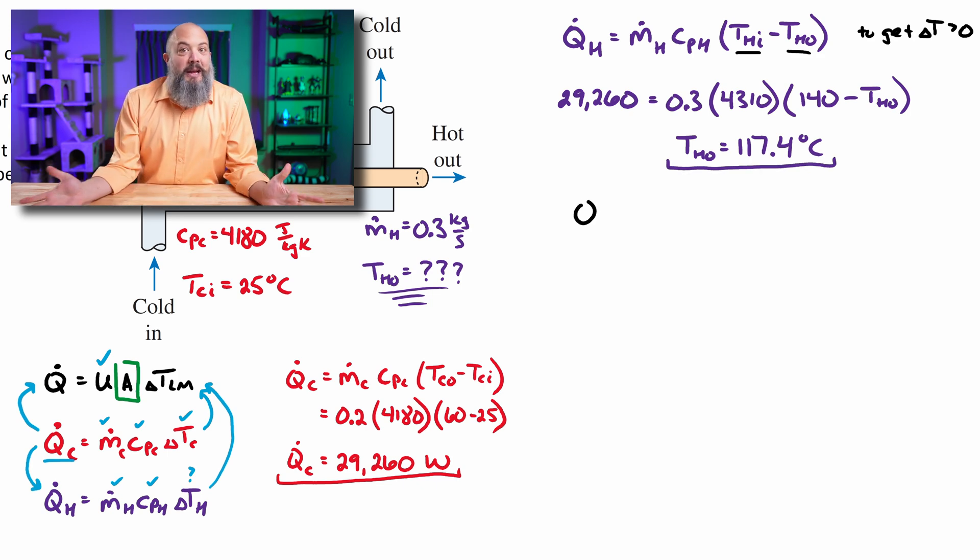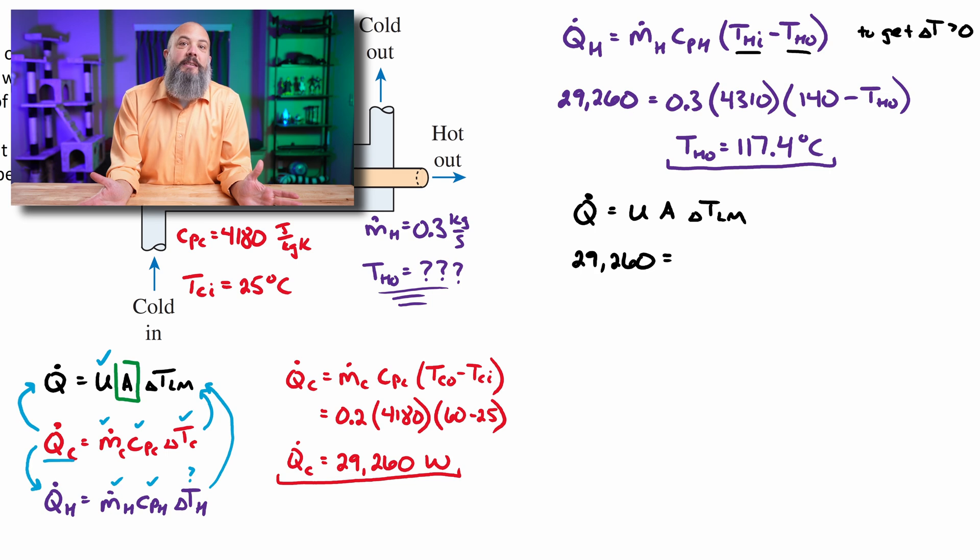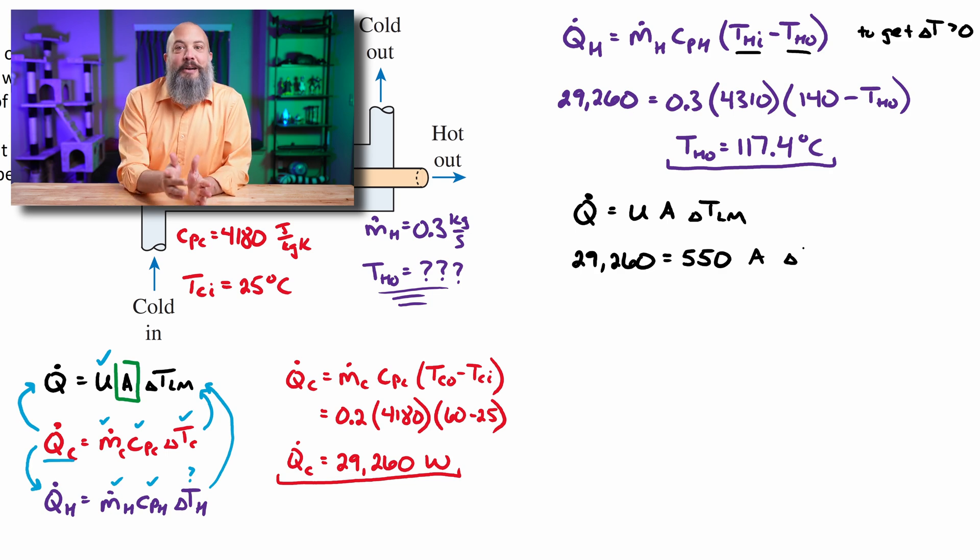And now starting to write out the third equation, Q dot equals U A delta T. This is the rate of heat transfer between the two surfaces, between the two pipes. We've got the 29,260 for Q, 550 for U, which was given. Even though it's not in my drawing, it was in the problem statement. You can go back to the beginning of the video and see. A is the final answer we're looking for. Delta T_LM, the log mean temperature difference.